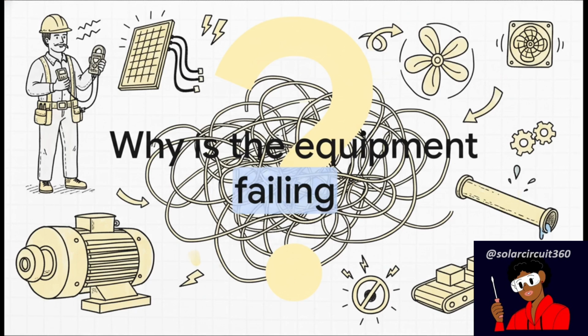But here's the kicker. The equipment attached to that motor is behaving like an absolute disaster. The pump isn't moving any fluid, the fan is barely pushing any air, or worse, the conveyor belt is sending product straight into a wall. It's kind of the ultimate mystery of cognitive dissonance for a tech. Every single electrical meter you have tells you the system is flawless, yet the machine is totally failing. So, what exactly is going on here?